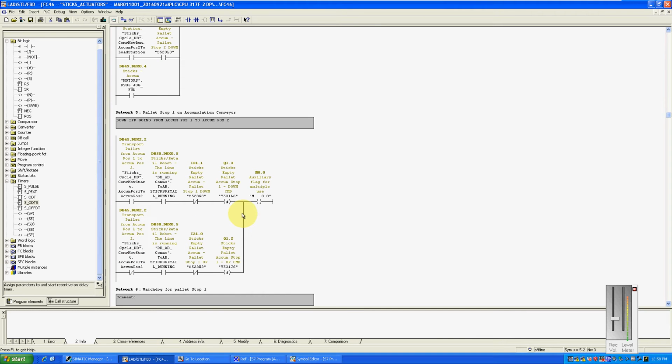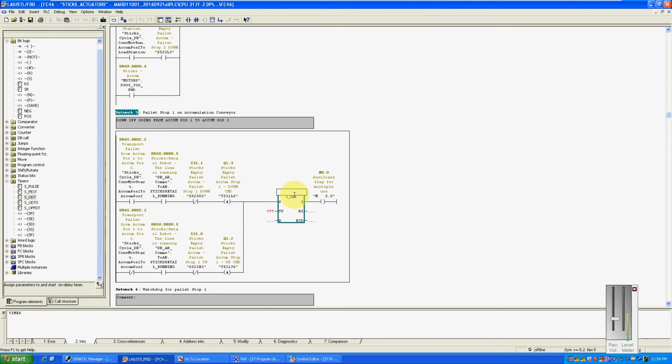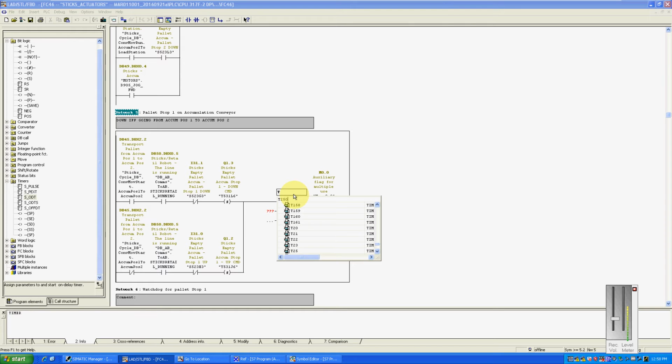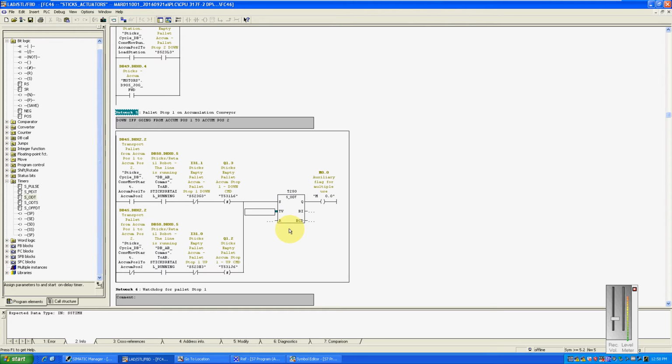So if you had to come here and said, yep, 250 is not used, and then later on in your program, generally in another function, you do an on delay timer, and you use T250 and S5T#3 seconds. Save that. It's happy, it compiles, it works. Well, it's not going to work the way you want it to. You don't know that it's been used elsewhere.